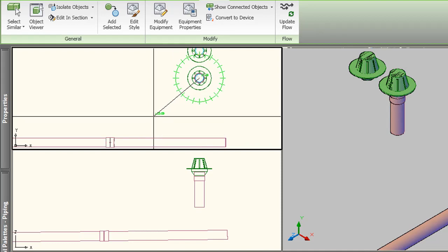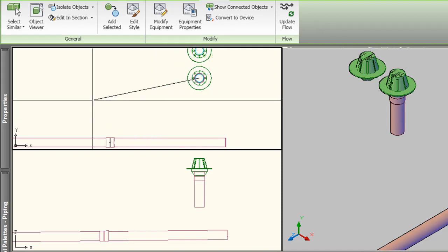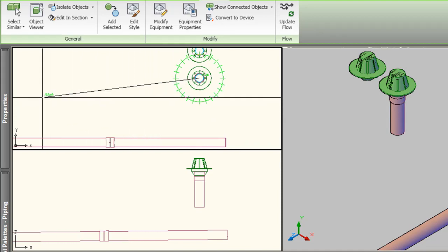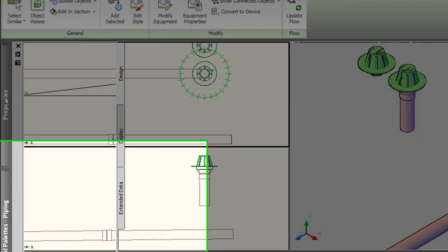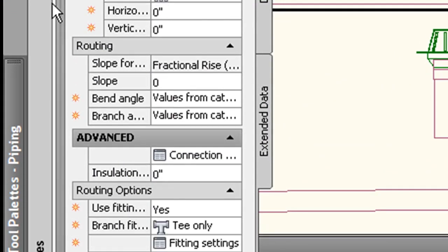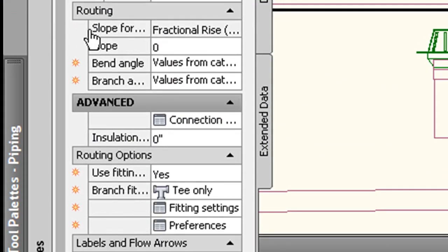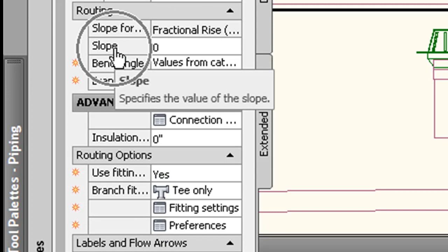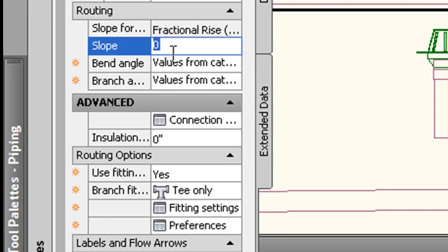But which one do I have set? Well, to find that out, on the fly, it's transparently. So without getting out of the command, we go to properties and we check. So in properties, actually, we're going to check two things. First, we're going to check the slope here. And it's a good thing I did because if I didn't change that, my slope on the lateral connecting to that branch would have been flat, which I don't want. So we'll change that to negative one eighth and leave it at negative one eighth because under my piping preferences, I set the slope format option to be inches per 12 inches.